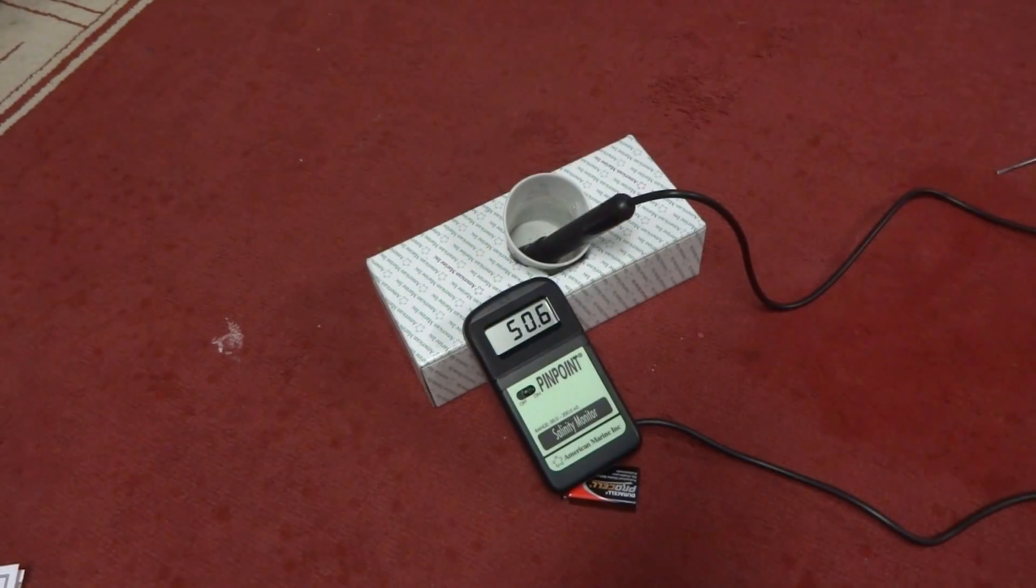Right out of the box the pinpoint salinity monitor was precisely at 53.0. I went ahead and messed with the adjustment screw in the back of the pinpoint monitor so I could throw it off for the purpose of this video and recalibrate it back to 53.